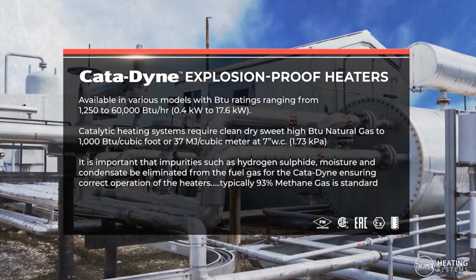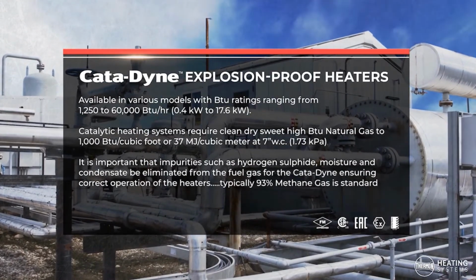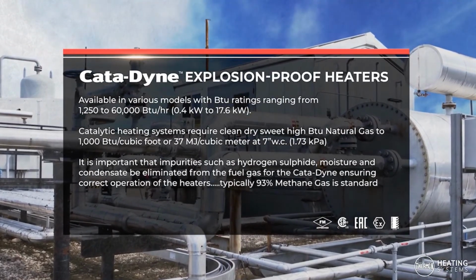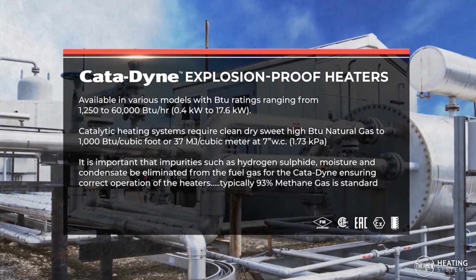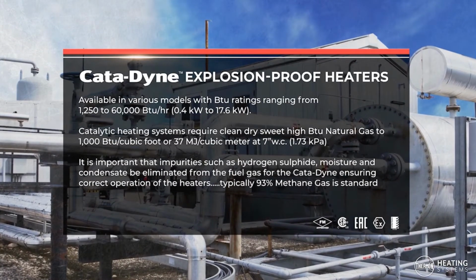Catalytic heating systems require clean, dry, sweet high BTU natural gas to 1,000 BTUs per cubic foot at 7 inches water column. It is important that impurities such as hydrogen sulfide, moisture and condensate be eliminated from the fuel gas for the Cata-Dyne, ensuring correct operation of the heaters. Typically, 93% methane gas is standard.